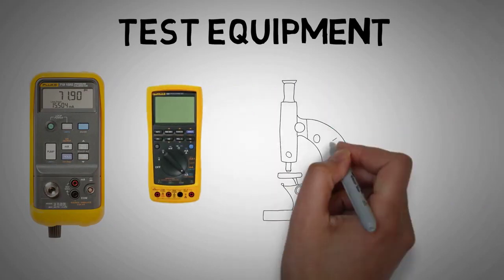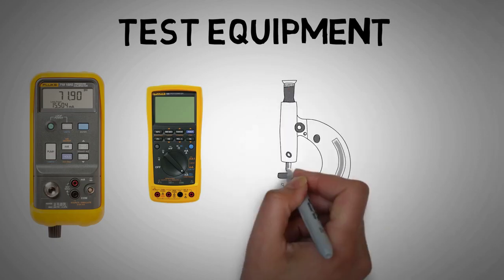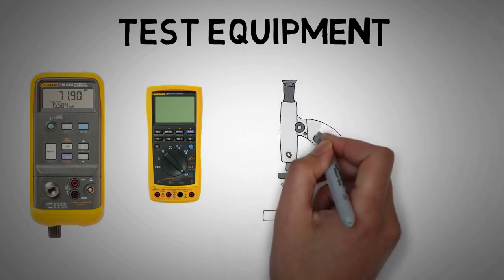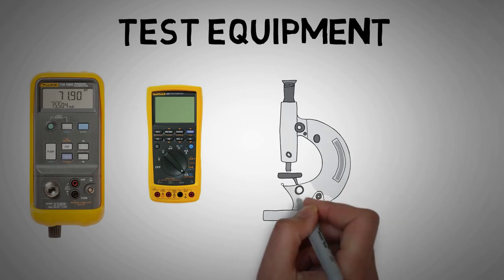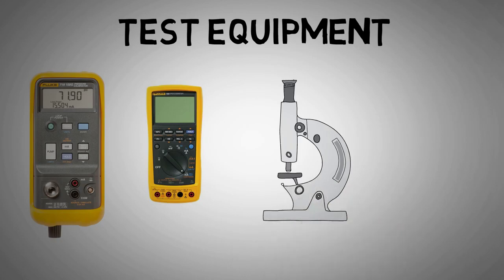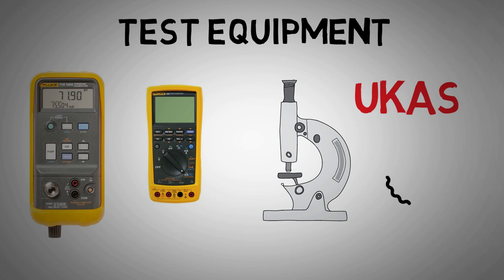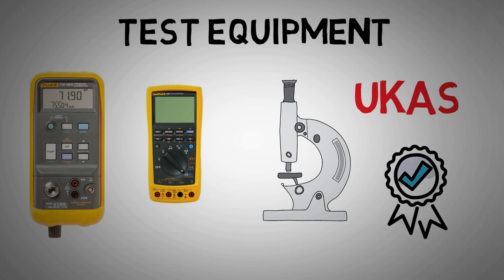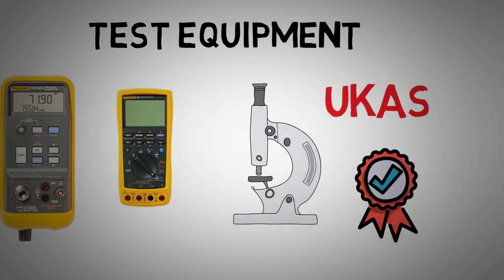Test equipment calibration is often carried out at dedicated calibration labs that will be accredited to certain standards depending on the country you're operating in. Here in the UK, UKAS is an accreditation body that will ensure a calibration lab is certifying its equipment to the appropriate standard. Let's look at how we would carry out a calibration using our vessel pressure transmitter as an example.